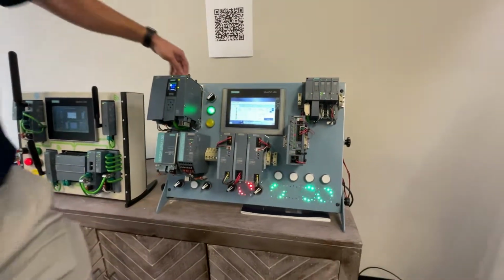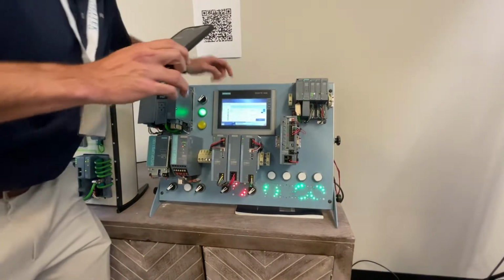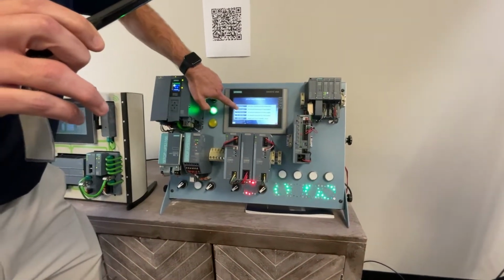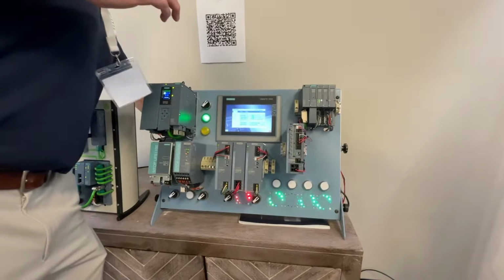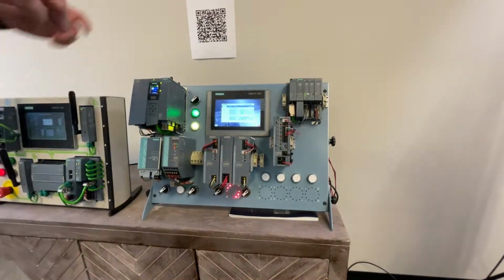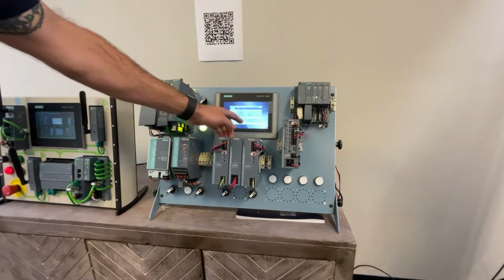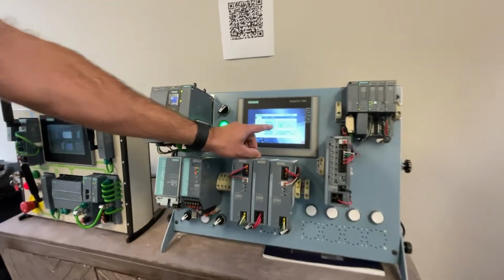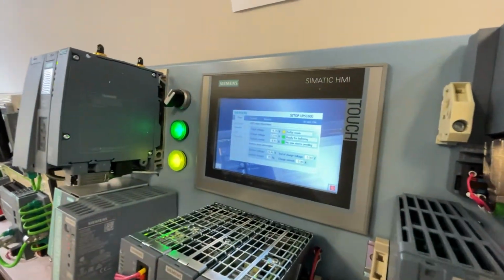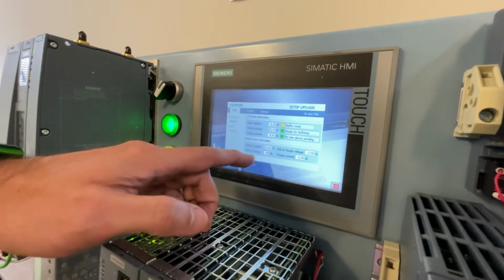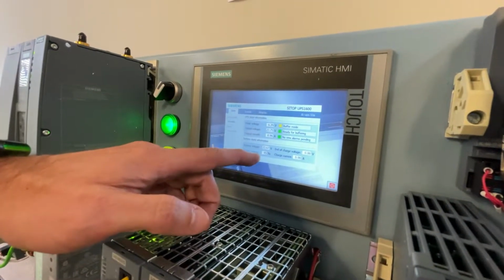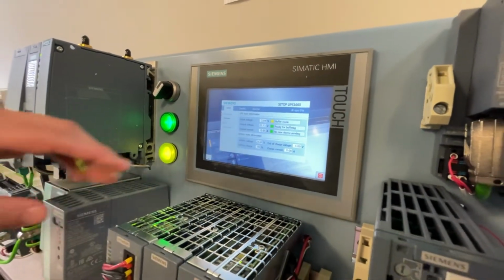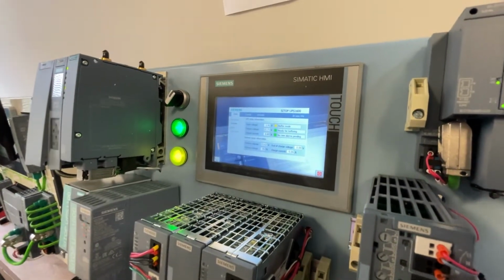So I'm going to flip the input breaker, see what happens here. Actually, let me change to this first too. Cut off the input, and now we're in backup mode, so you see the input voltage is going to 0, but our output is still stabilized at 24 volts. You see our battery is about 95% charged and it's starting to dip a little bit, but that UPS module is stabilizing that output to be still about 24 volts to the loads.